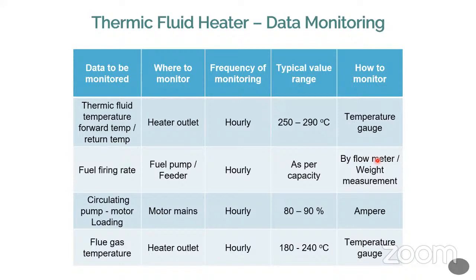So we have the thermic fluid heater temperatures, both the forward temperature. Forward temperature means the output of the TFH to the process, and the return temperature from the process to the tank. That is called the return temperature, 240, 220. Okay, like that. So it should be properly monitored with the help of a thermal imager or thermography, or even temperature gauges fitted in the system itself. It is in the typical range of 250 to 290. Sometimes it could be 300.